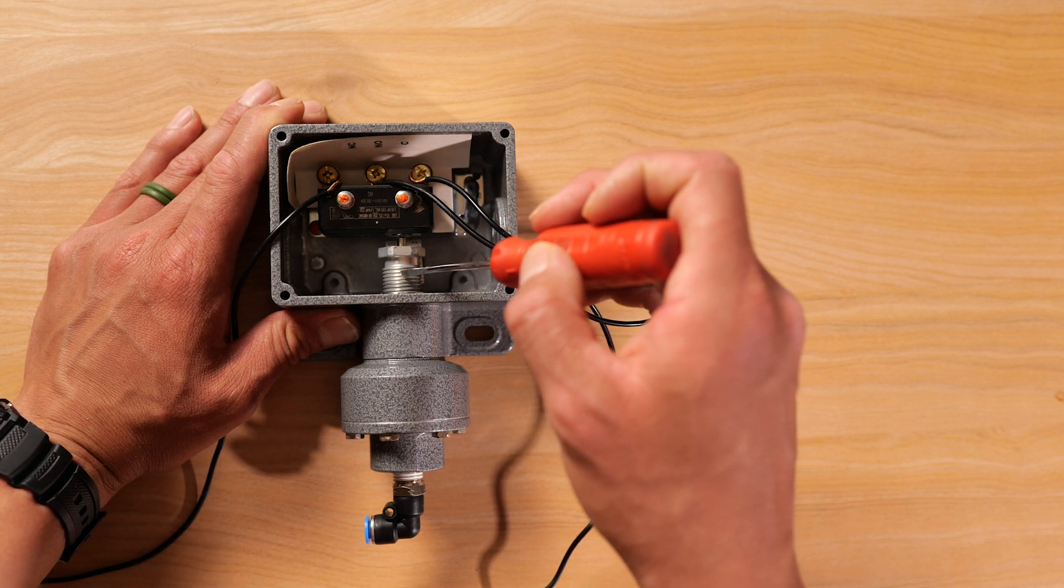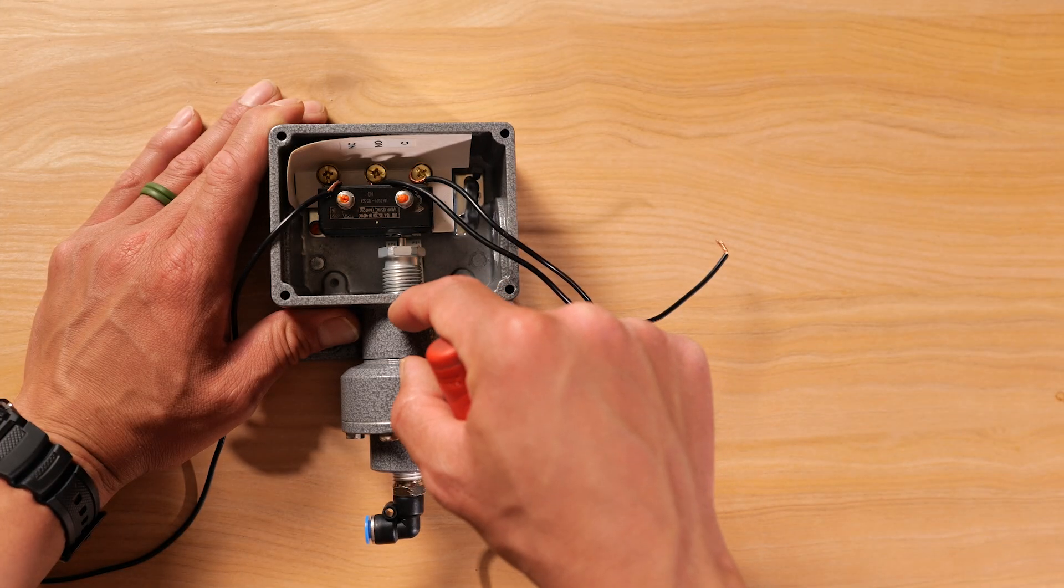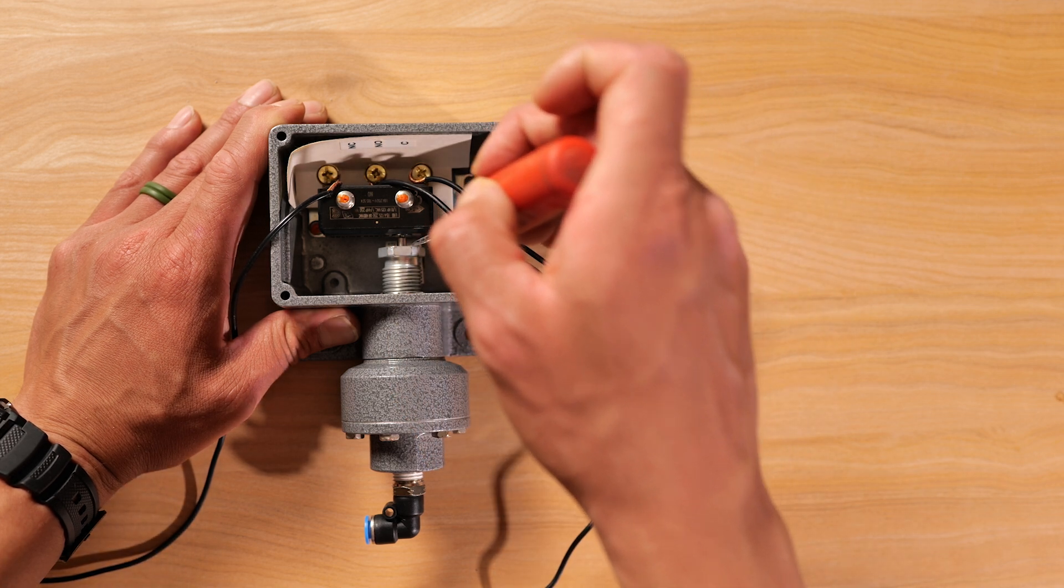And the further you go down, the more pressure you're applying on the range spring. So the further you go down, the more pressure, the higher set point you'll have.